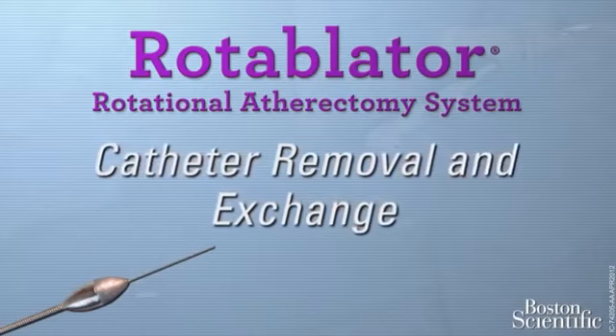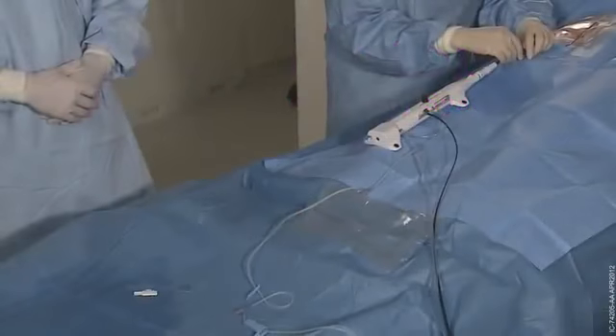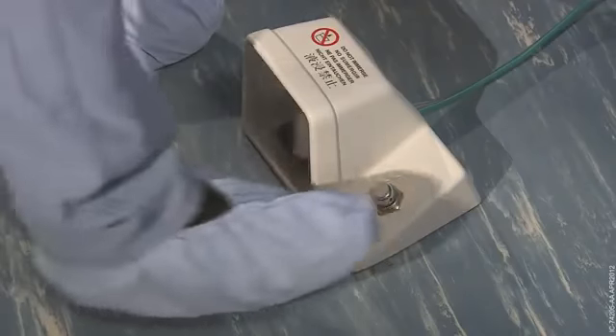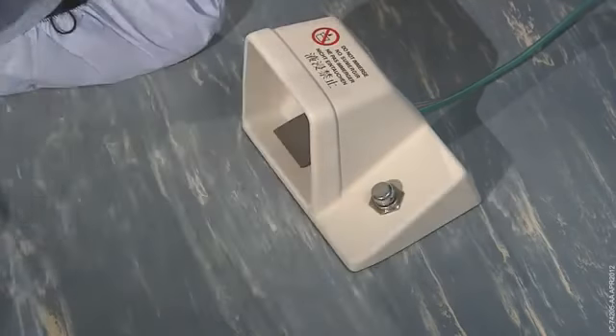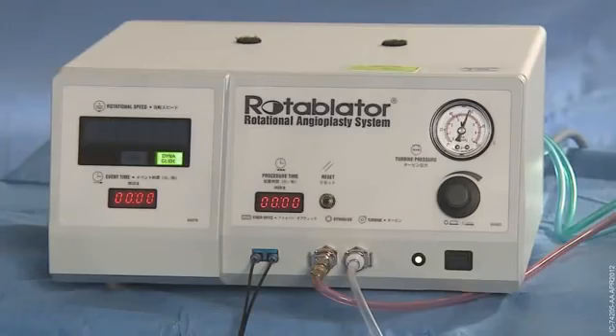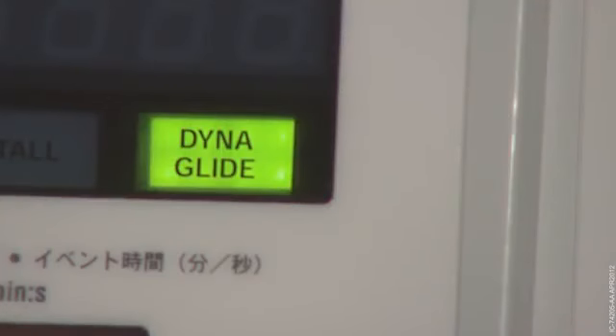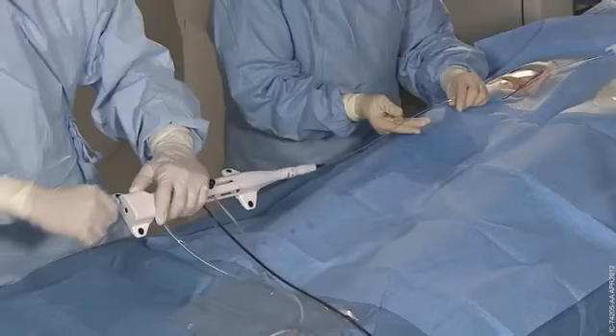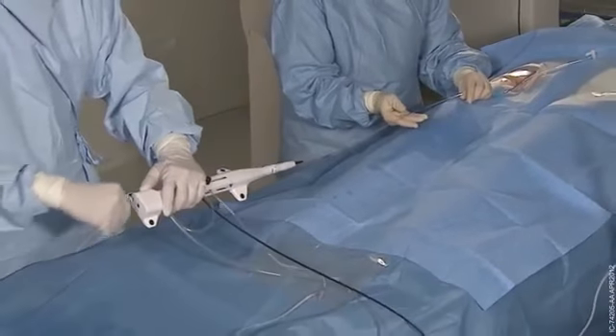To remove the burr catheter from the patient, put the system in the Dynaglide mode by stepping on the Dynaglide foot switch. This reduces the rotation speed to between 60,000 and 90,000 RPMs. The guide wire must be held firmly whenever in Dynaglide mode.